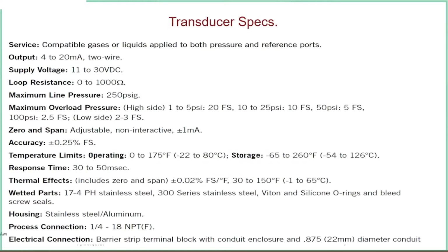This DP transducer could be used with pressure or with liquids. It has Viton and silicon O-rings inside. And if it was liquids and you had to bleed it, there are a couple of screws on the side of the DP device, the transducer, that you could actually bleed out the liquids until you got rid of all the bubbles in the line and so forth. But in our case, we didn't have to do any of this, just looking across the catalyst.